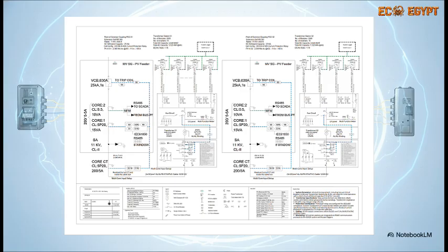Now this isn't just some rough sketch, it's a wildly precise electrical schematic. It shows exactly how the power from those 115 kVA inverters routes directly into the main distribution panel, flows through these massive 4-pole motorized circuit breakers that are designed to handle thousands of amps, and integrates perfectly with the surge protection devices before finally making its way up to those medium voltage transformers.